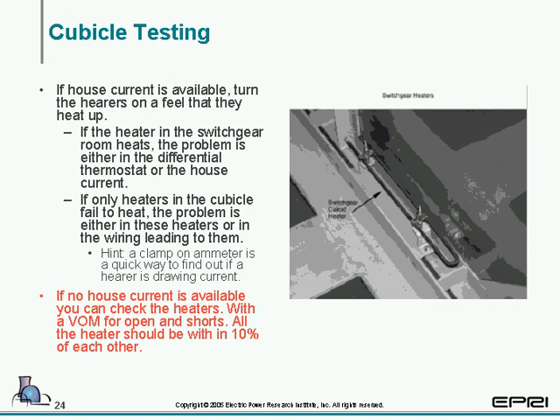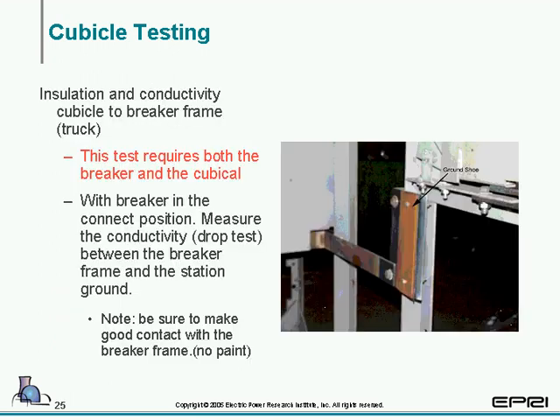And generally, as a rule of thumb, you would expect that the heaters would be within 10% of each other, and you'd use basically the same for checking for fans. More on testing.